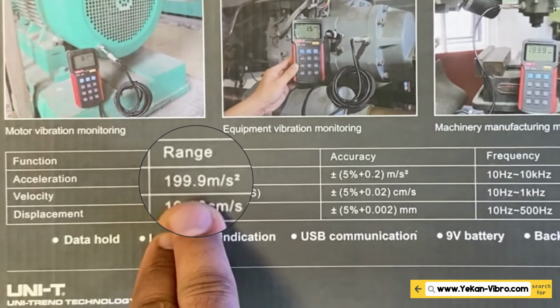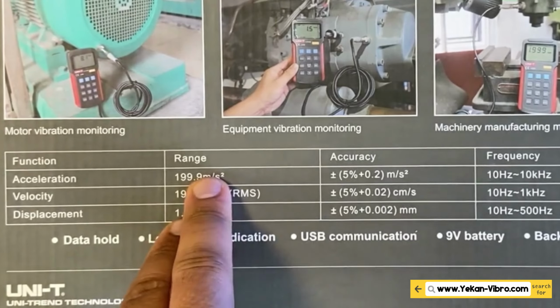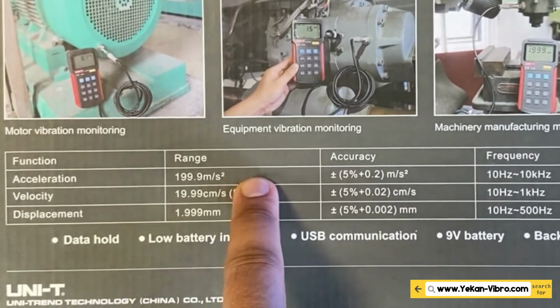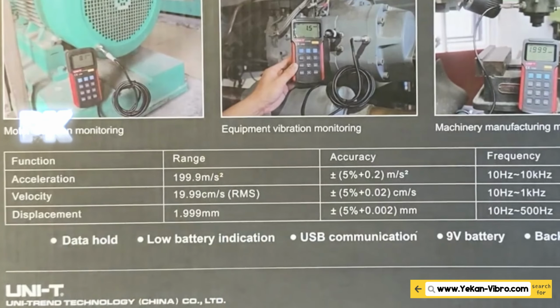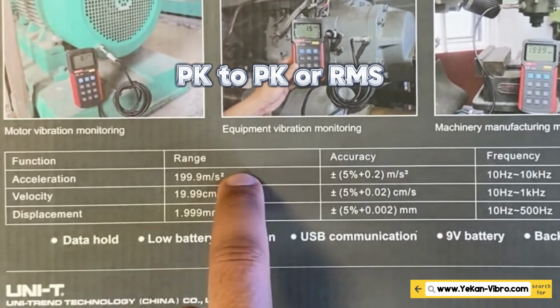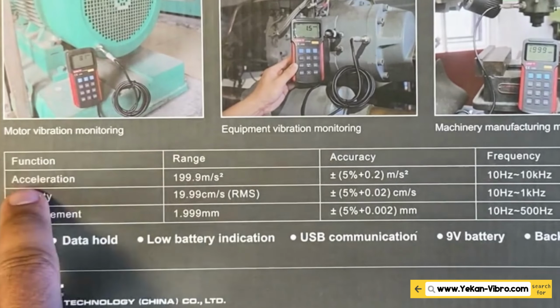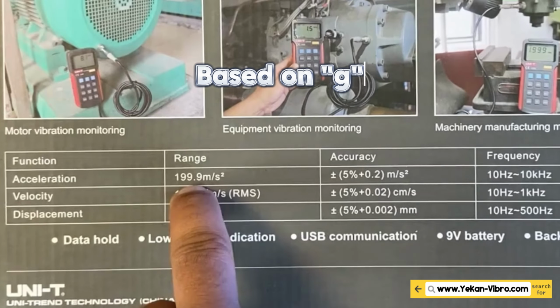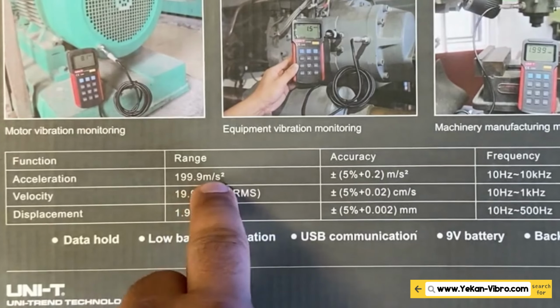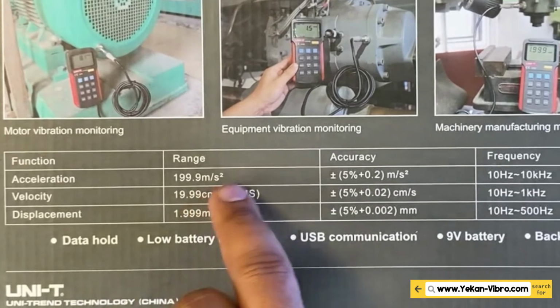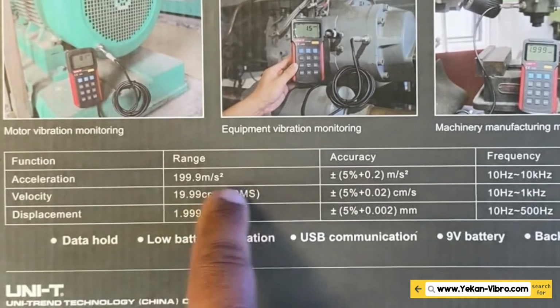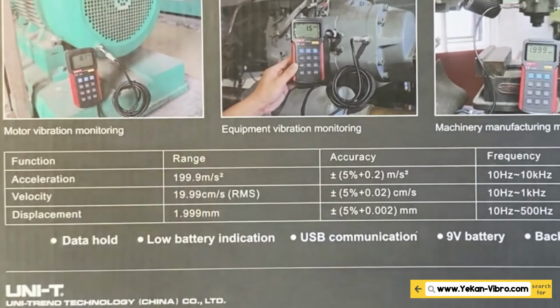In acceleration it says I measure up to 199.9 meters per second squared. Unfortunately, this meter per second squared is only peak. That means you cannot convert it to, for example, RMS, the option does not exist. Or if you want vibration acceleration based on G, unfortunately it does not have unit conversion. And the peak also does not convert. And this itself may cause you trouble.